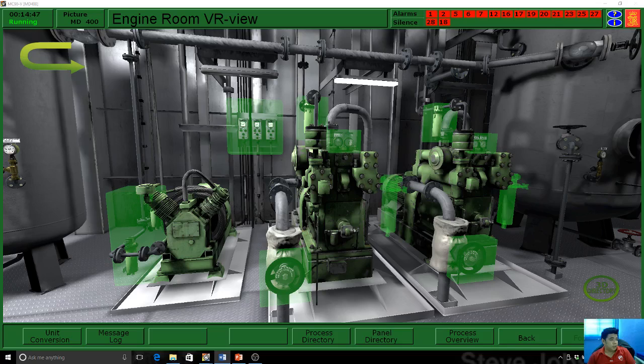I'm just reading the book for the Kongsberg. The emergency air compressor is air cooled, meaning this one here. That's the purpose of the fin. One thing you should remember when you go on board: don't paint it. You just clean it, clean and clean, because the thicker the paint, the more it will lose its heat transfer and cooling capabilities. Maybe you're making it nice, but eventually you're destroying the compressor by making it thicker.